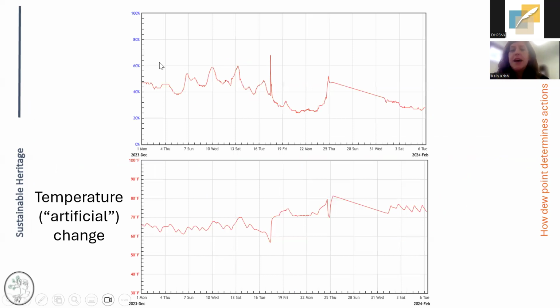On the opposite end, this was the other relative humidity graph, again, having that drop in RH. Didn't really necessarily see anything going on in dew point, but we did notice that something had happened with the temperature set point, and we'd ended up heating to about 75 degrees in February. So because we were heating so much dry air, we were driving that relative humidity back down. So in this instance, we didn't need to fix anything. We didn't need to address an issue with a component. We just needed to bring that temperature set point back down so that our relative humidity was kept high enough.